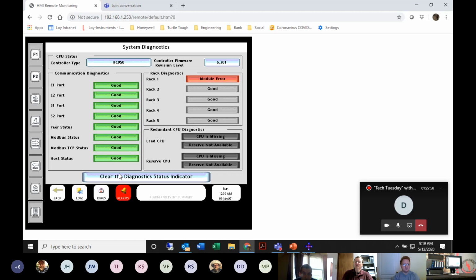This allows you a very, very quick diagnostic of the system to show you what's going on with not only the CPU, so we have the communication diagnostics, but it also shows you all the modules in the rack that are programmed out in the field. It shows you the revision of the firmware in the HC900 and the controller CPU type. So in this one we have a C50.